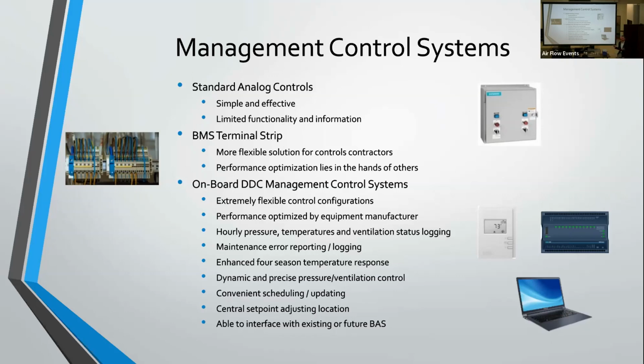So you might want to consider something like an onboard management control system or a DDC control system provided by a manufacturer. These are extremely flexible control setups. You can set things like scheduling, occupancy set points, occupied and unoccupied set points, building pressure set points, unit cycling set points, and economizer set points. The list goes on and on of things you can tweak on your controls to optimize the energy efficiency of that unit.